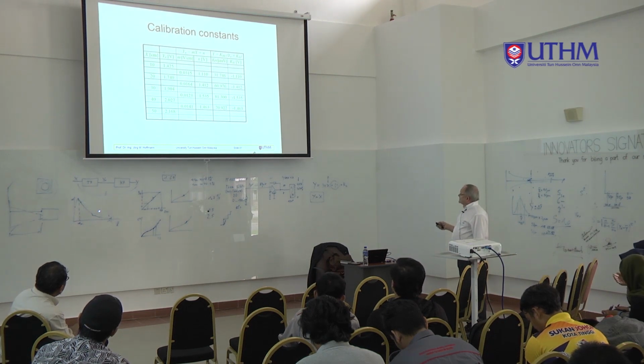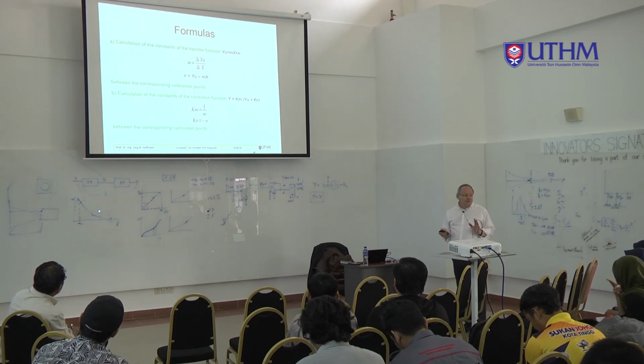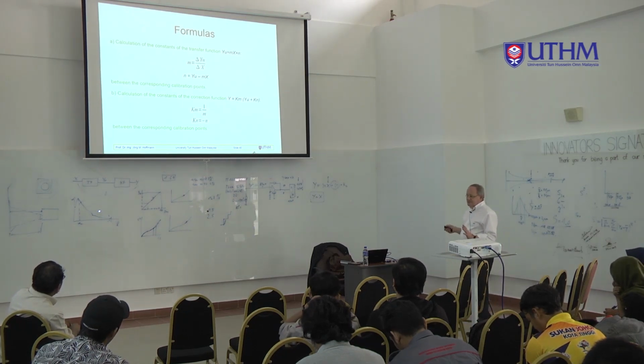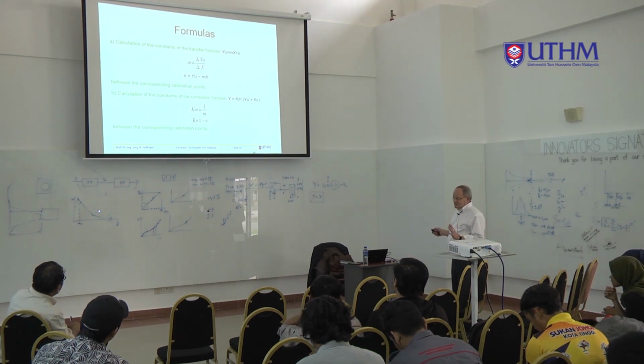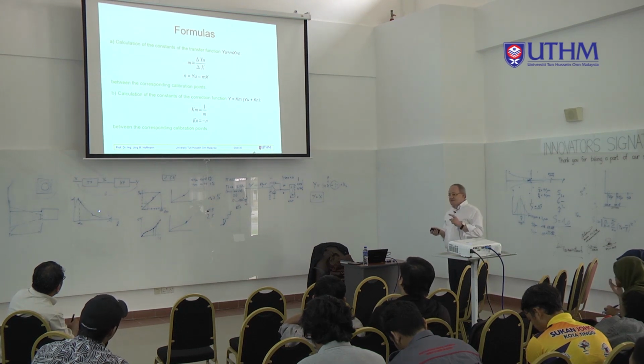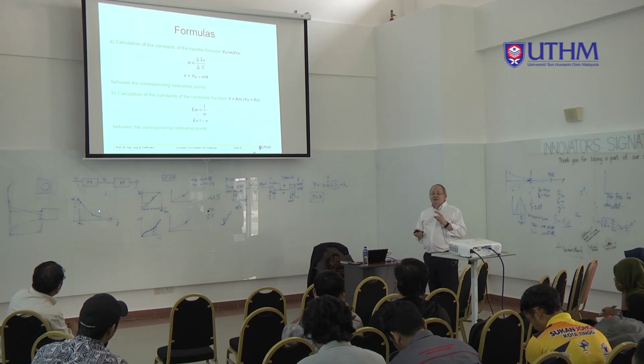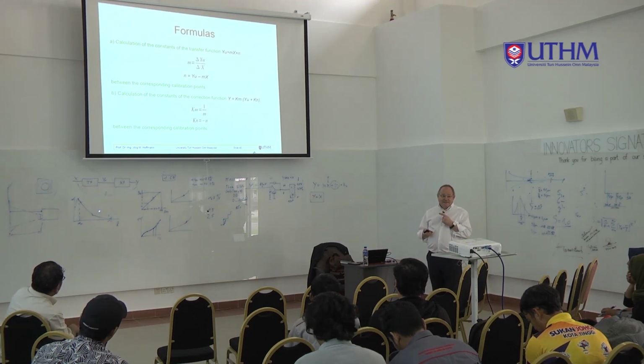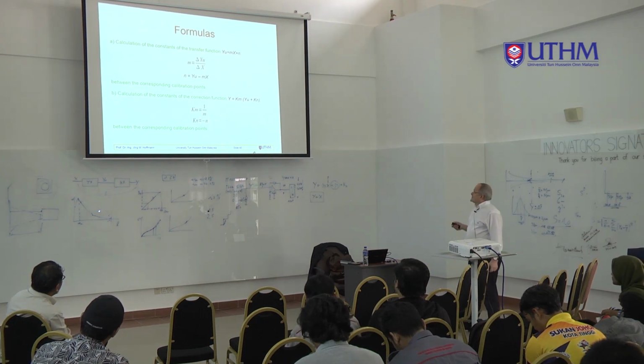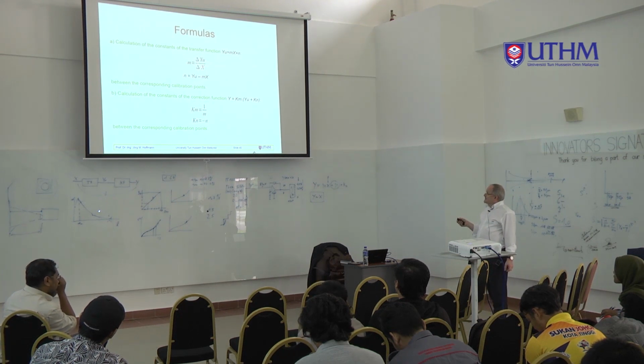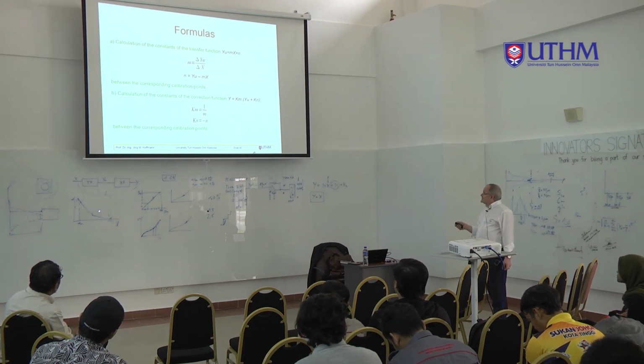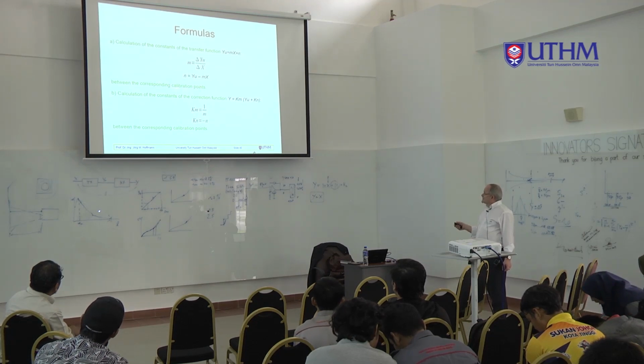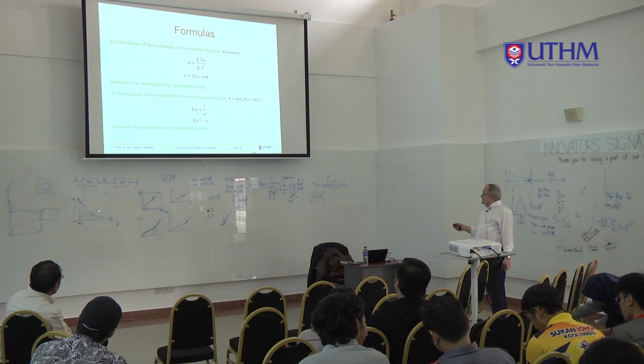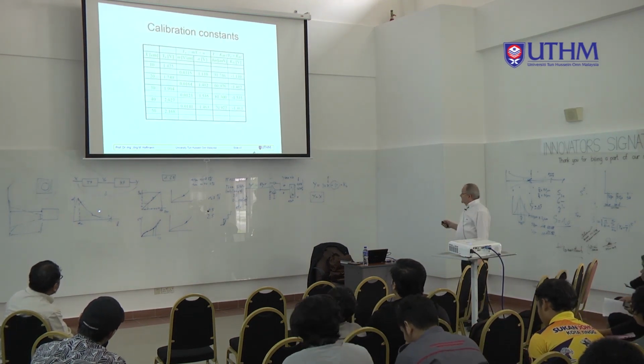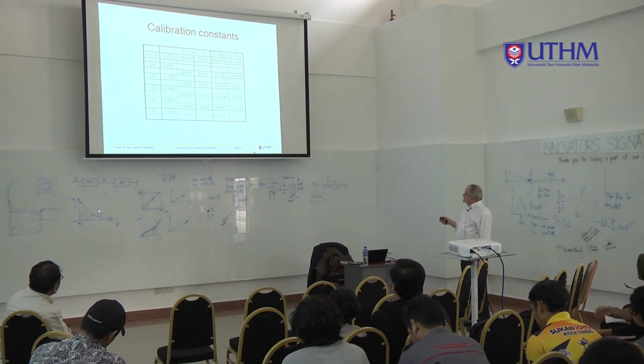So the mathematics, you see, it's absolutely simple. Absolutely. That is primary school, I think so. In the end of the primary school, you should know that. But, and that is also what I say every time to German students, you must know what you do with these formulas. The formulas are easy, but you must know what you do with the formulas. M is delta y uncorrected divided by delta x. N is y uncorrected minus mx. And that is then between the corresponding calibration points. And then Km is 1 divided by m, Kn is minus n. And you see you have one line less than calibration points.